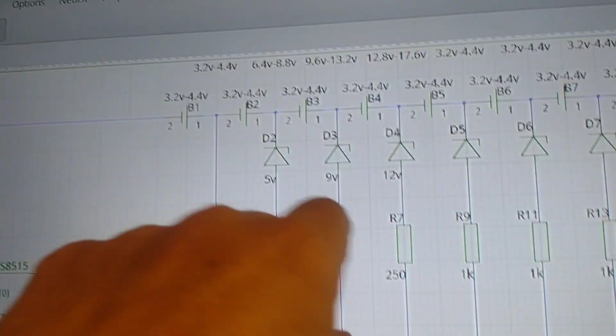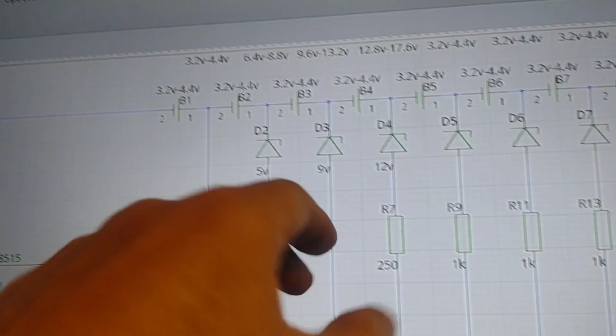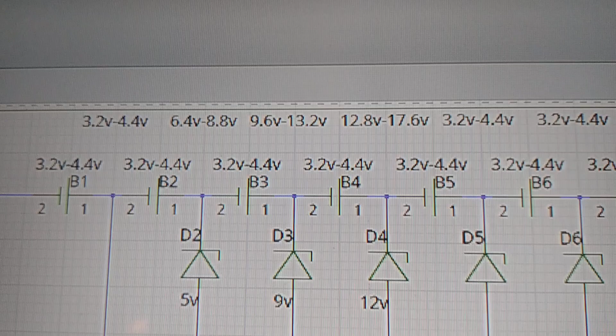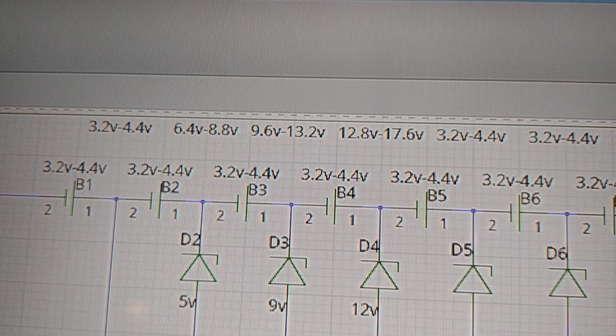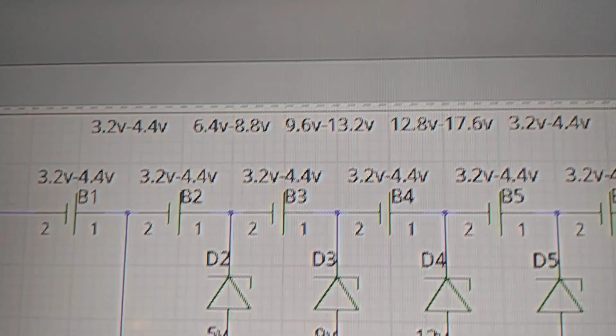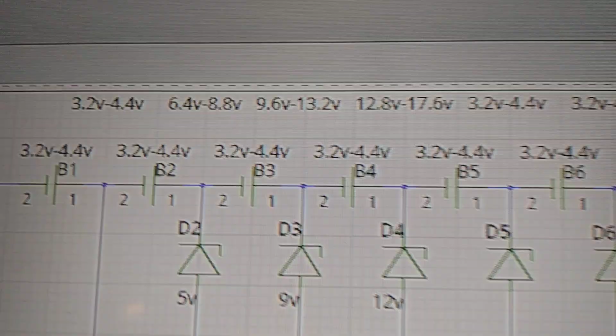Now you have to do it like that because you're measuring this cell voltage here, but you're measuring it against the voltage of the previous cells, and these could be at any voltage, you see. So that's why the voltage range is 12.8 to 17.6, and not just because the voltage range of the cell is only like, what's that, 0.8 volts of the cell, right? Yeah, 3.2 to 4.4 is, no, it's not. It's 1.2, isn't it? So that's 1.2 volts, but the voltage range is well over 5 volts.